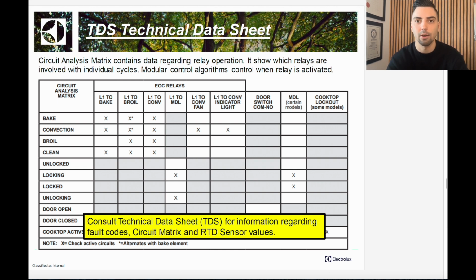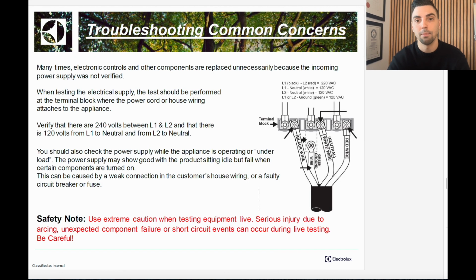Being able to understand how to read these will assist you to troubleshoot and diagnose your appliances appropriately and be able to finish a service call, hopefully in 1 to 2 visits. Many times electronic controls and other components are replaced unnecessarily because the incoming power supply was not verified by the technician. So when testing the electrical supply, the test should be performed at the terminal block where the power cord or house wiring attaches to the appliance. You want to verify that there are 240 volts between L1 and L2, and that there is 120 volts from L1 to neutral and from L2 to neutral.